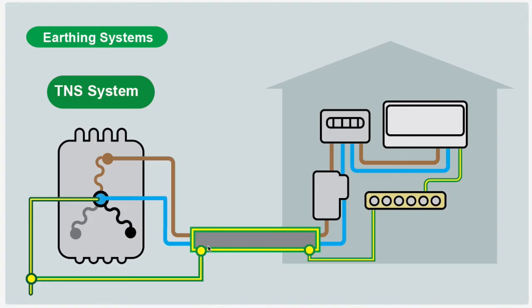covering is connected at the earthing point at the transformer. There's a lead from this cable in your property, and this is connected to your main earthing terminal, which then goes to your consumer unit and onto all the other appliances around the house. That's your TNS system.